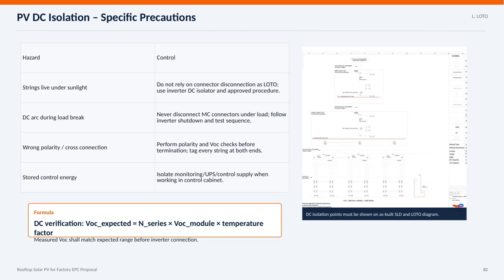On this slide, we're focusing on the critical precautions for PV DC isolation, especially under lockout/tagout or LOTO procedures. First, it's important to understand that strings remain live when exposed to sunlight, so you cannot rely solely on disconnecting connectors for safety. Instead, always use the inverter's DC isolator along with an approved procedure. Next, to avoid dangerous DC arcs during load break, never disconnect MC connectors while under load. Follow the proper inverter shutdown and test sequence.